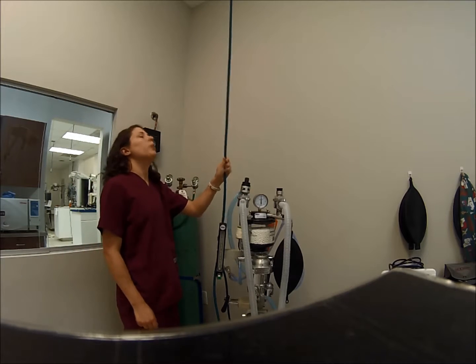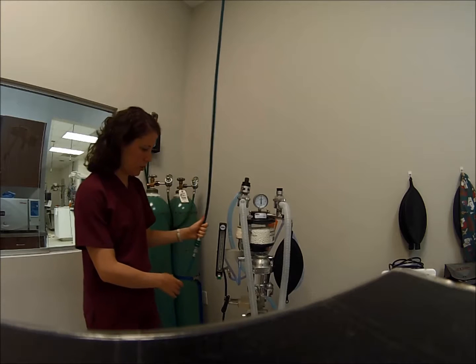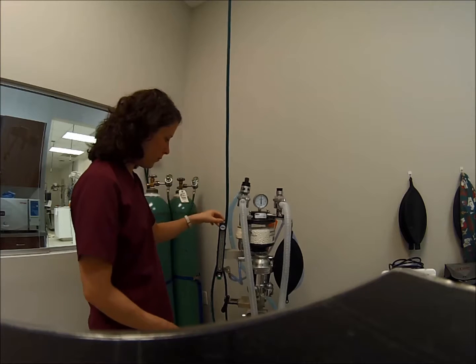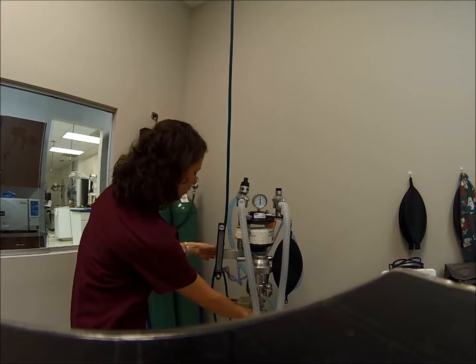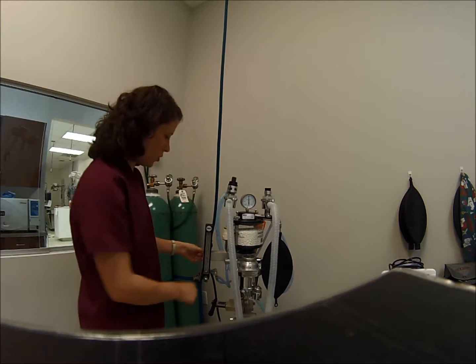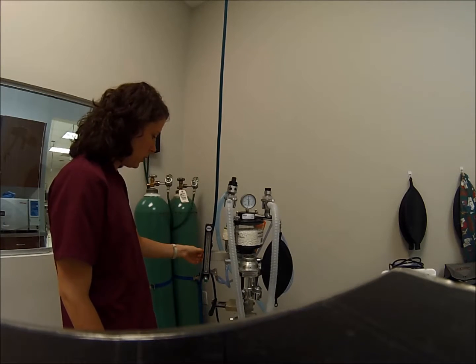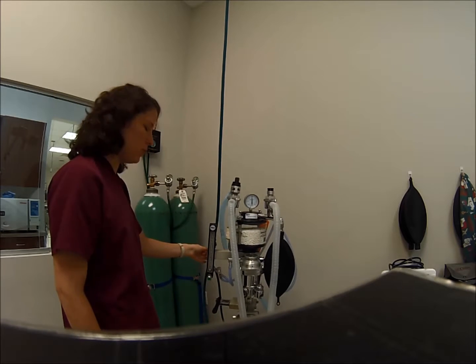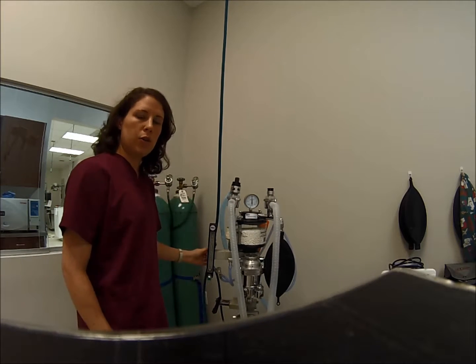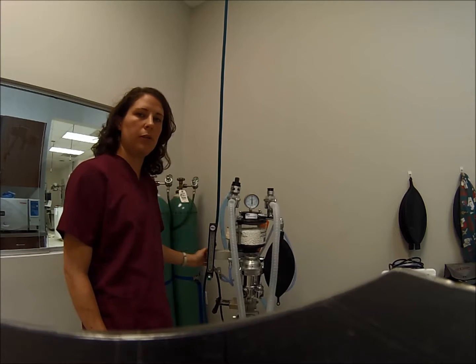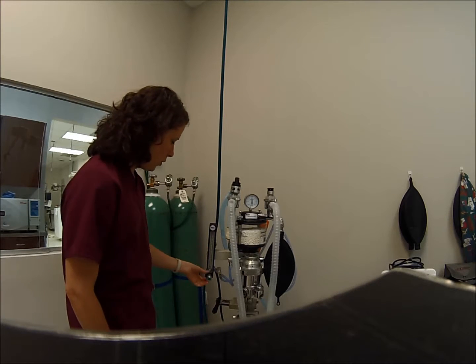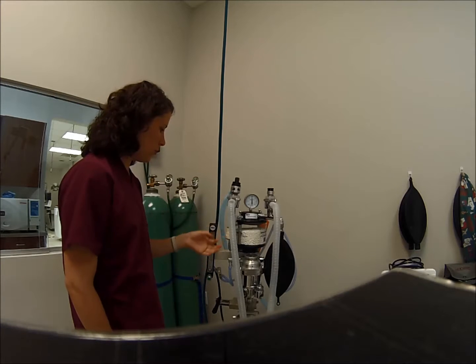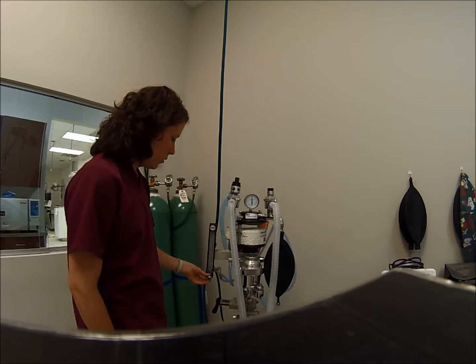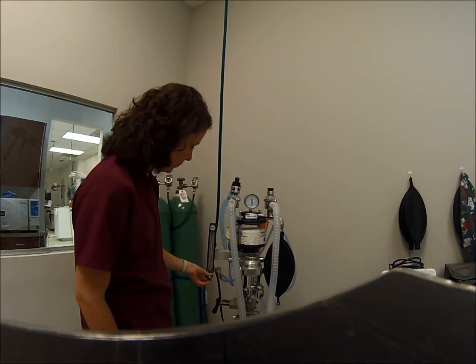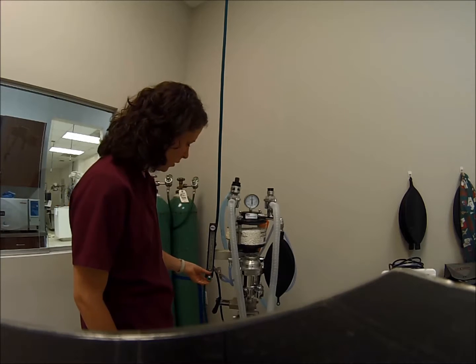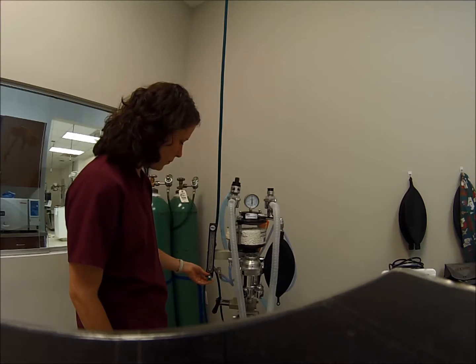This is our hookup that I have here attached to this anesthesia machine. First we have our oxygen flow meter right here, which is measured in liters per minute. This further reduces the pressure in the system down to 15 psi, which is close to atmospheric pressure and well tolerated by patients. You can control how much oxygen is going through the patient via the flow meter by turning the knob to the desired measurement.